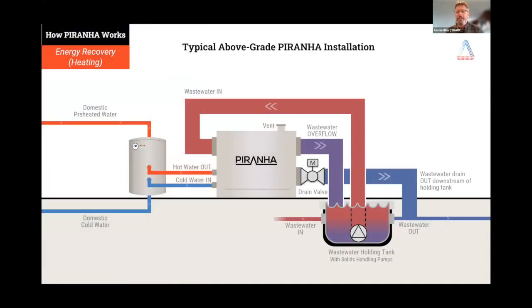This is a line diagram, I'll try to keep pace with these technical slides. This is what a typical Piranha looks like when installed. There's a wastewater holding tank, which acts as a thermal battery. For a typical apartment building, there's usually one sanitary outflow; we intercept that and side-stream it into a holding tank, sealed and vented so there's no smell, and that acts as our thermal battery.